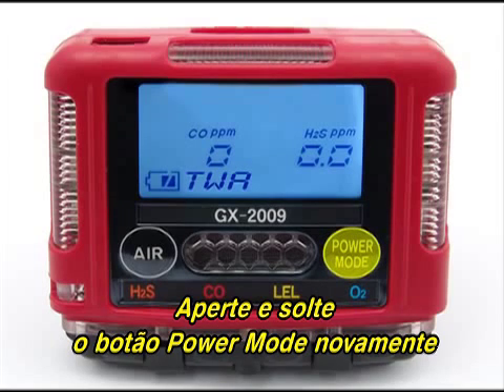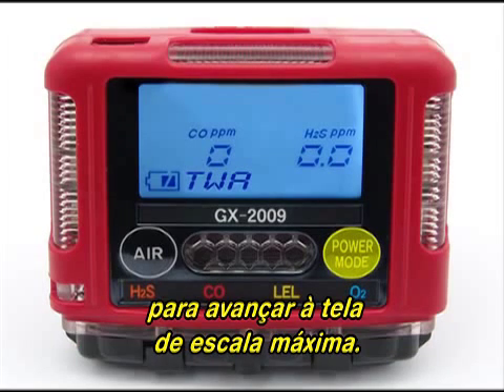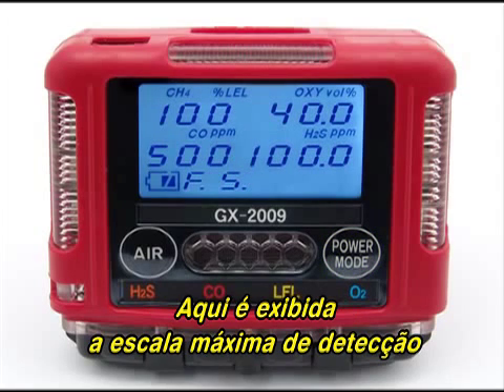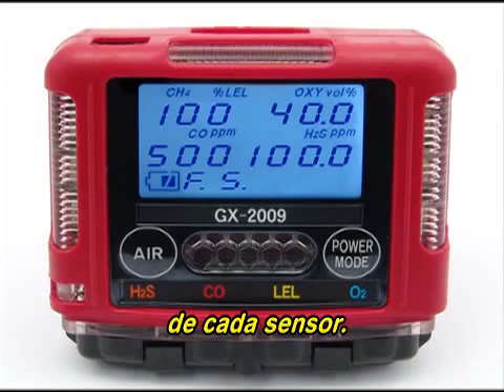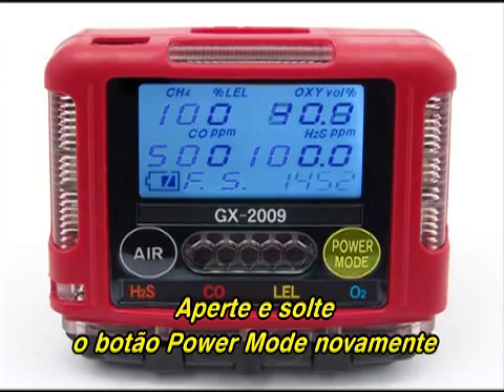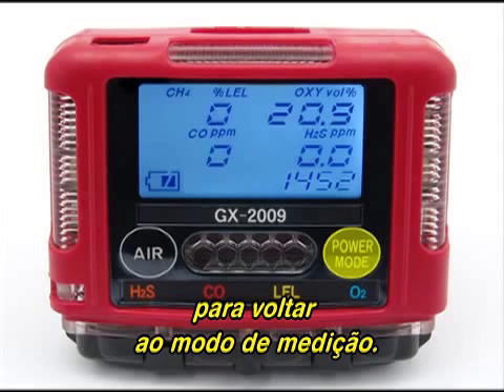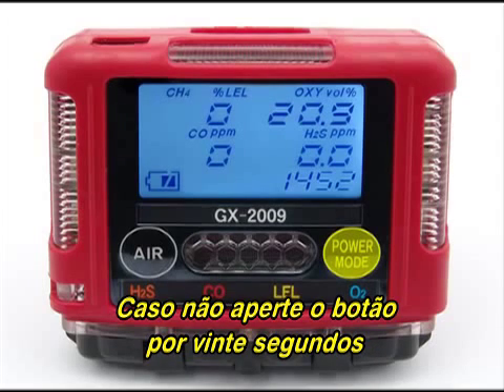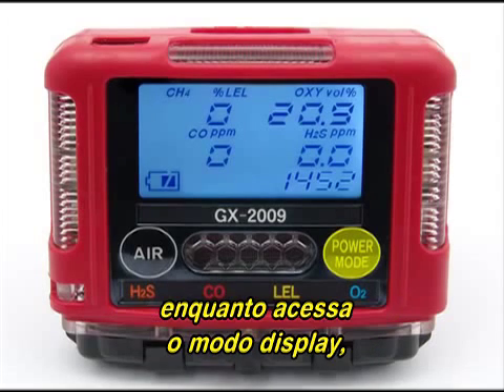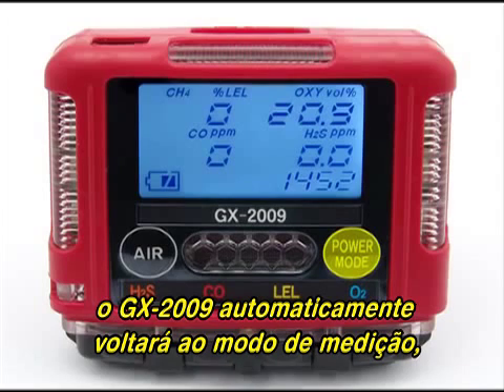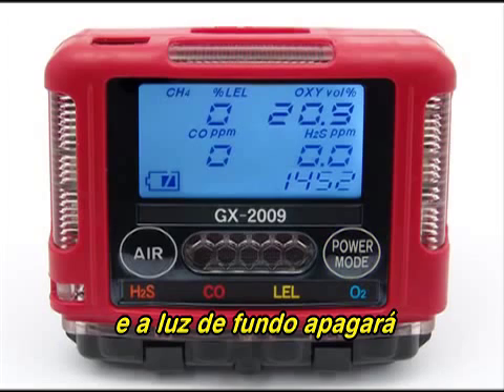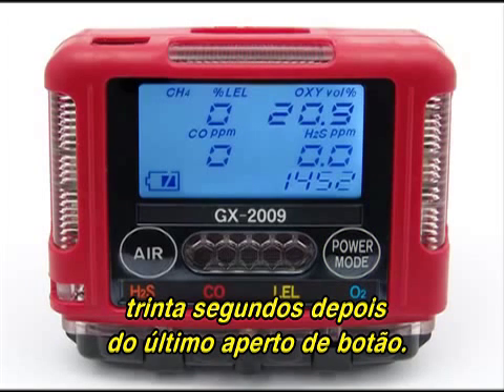Press and release the power mode button again to proceed to the full scale screen. The detection range full scale value for each channel is displayed. Press and release the power mode button again to return to measuring mode. If you do not press the button for 20 seconds while in display mode, the GX2009 will return to measuring mode automatically, and the backlight will turn off 30 seconds after the last button was pressed.